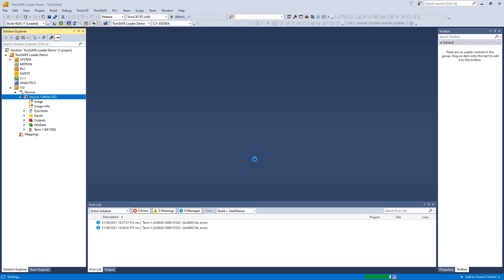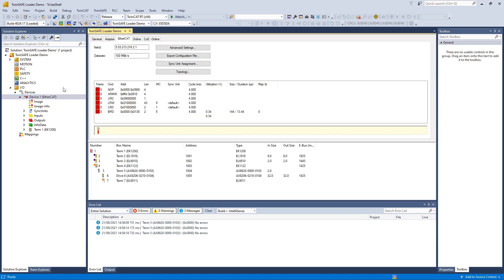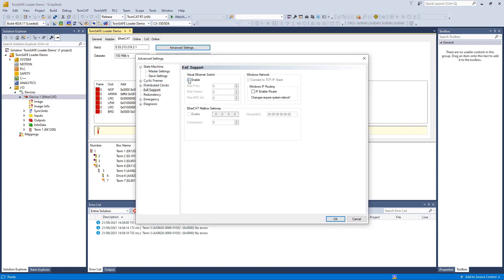We start configuring the system. When asked for free run, we choose yes, and then we go over to the EtherCAT adapter to the advanced settings, and then in the EoE support page, we enable the virtual Ethernet switch and enable the IP enable router checkbox. We configure our EtherCAT Mailbox Gateway with a new address: 192.168.100.254.